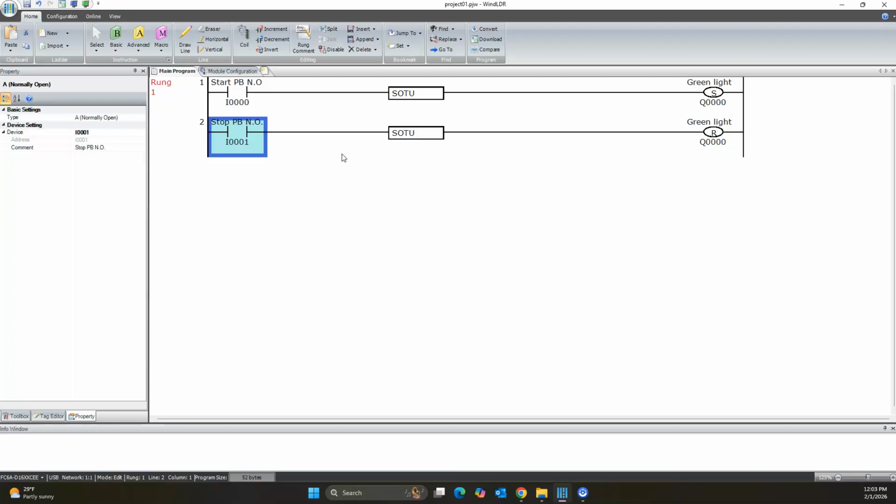So these single outputs, whether it's up or down, give you some ability to gain functionality you need with bits that might not otherwise behave the way you need them to behave, right? So it lets you treat things like momentary buttons even if they aren't momentary buttons. We could use a maintained selector switch and treat it like a momentary button using one of these single outputs.